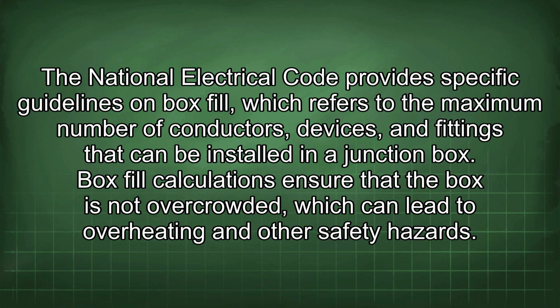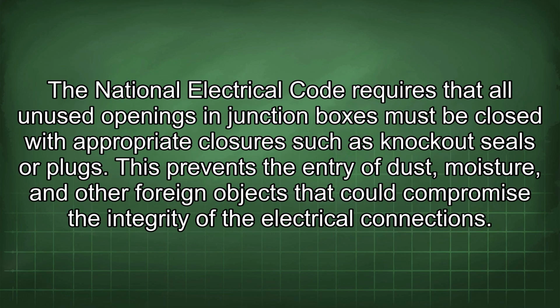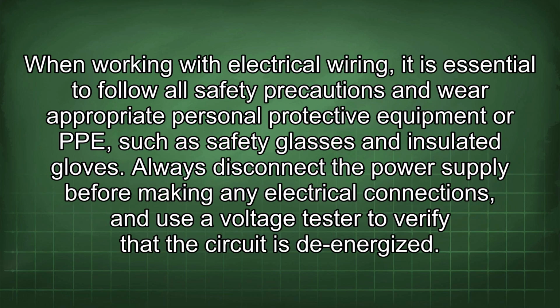Box fill calculations ensure that the box is not overcrowded, which can lead to overheating and other safety hazards. The National Electrical Code requires that all unused openings in junction boxes must be closed with appropriate closures such as knockout seals or plugs. This prevents the entry of dust, moisture, and other foreign objects that could compromise the integrity of the electrical connections. When working with electrical wiring, it is essential to follow all safety precautions and wear appropriate personal protective equipment, or PPE, such as safety glasses and insulated gloves.